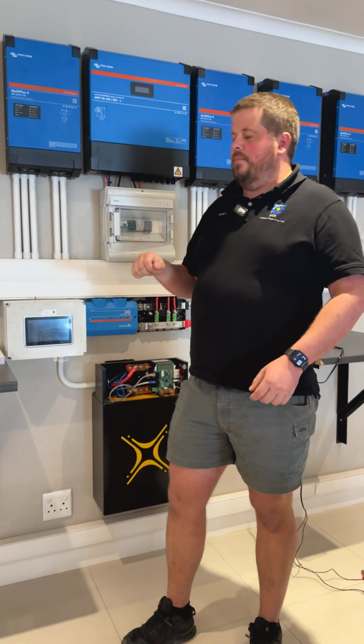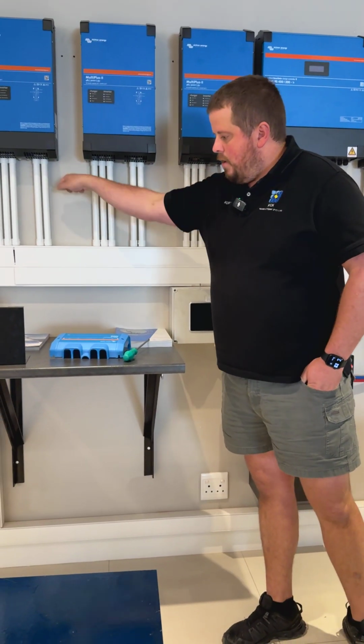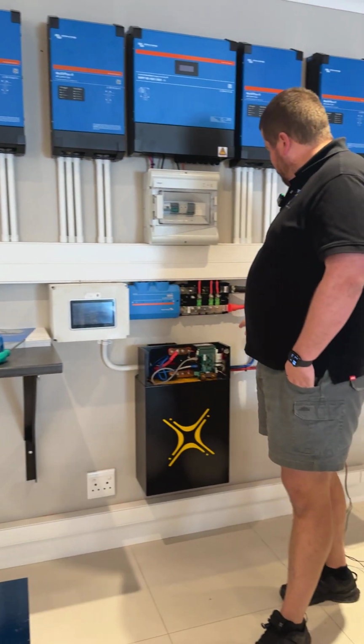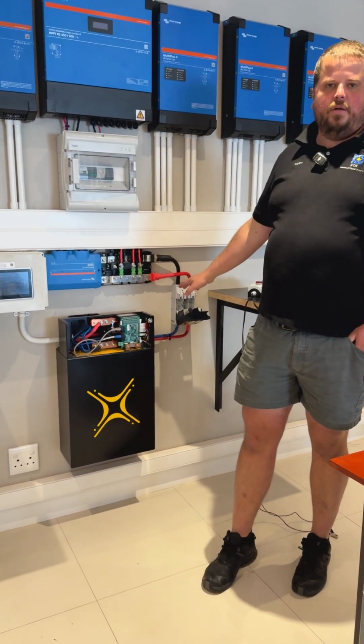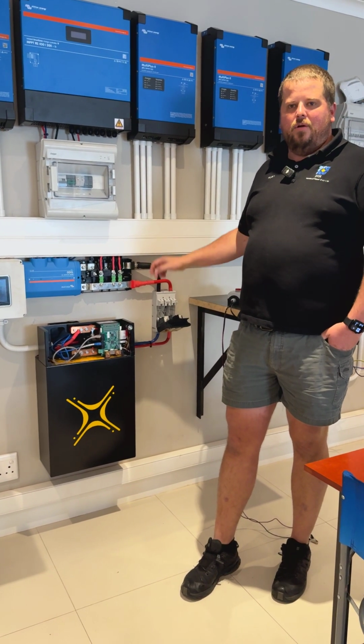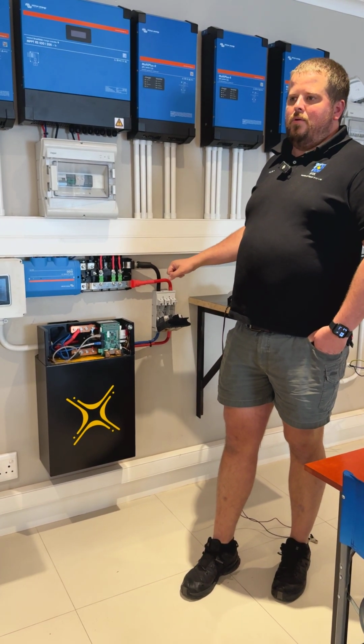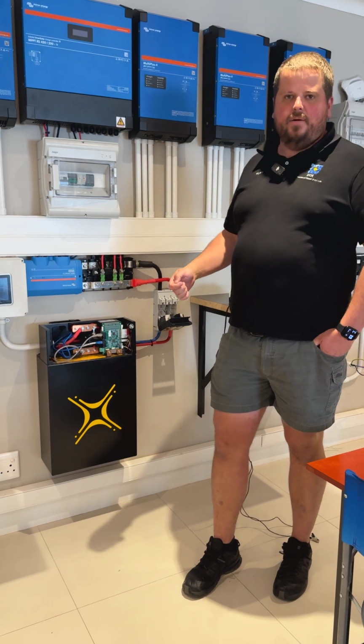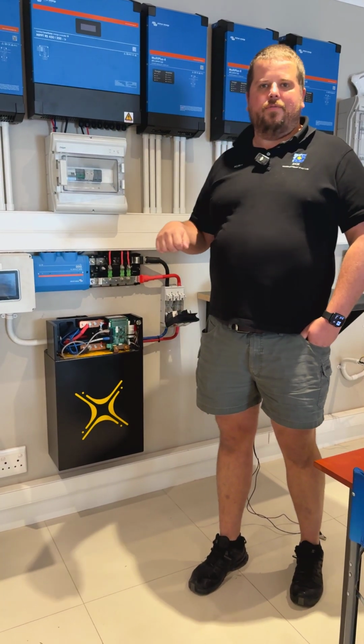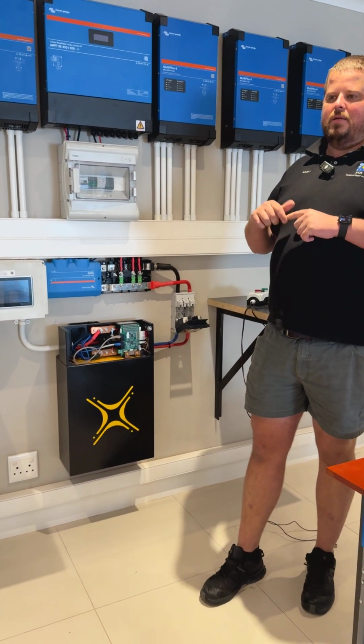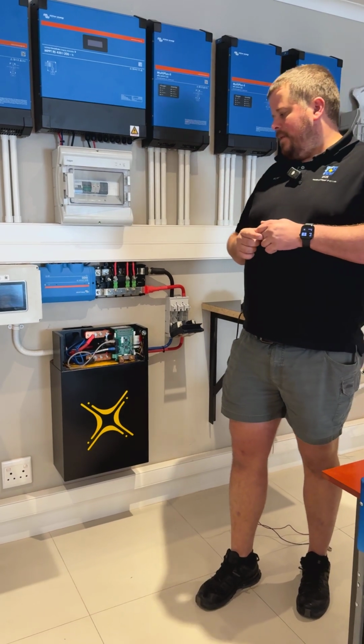But there's one problem: if you close it afterwards, you actually damage your fuse holder. This fuse holder, if you read correctly, is not meant to disconnect and connect under load. It's just a disconnect or isolating point, not to disconnect or connect under load.